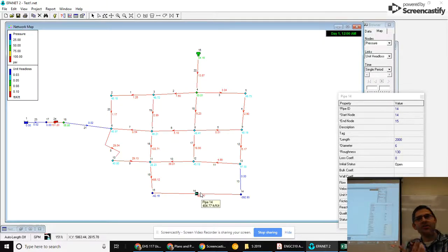So now if it's closed, I lose. But I can just lay it in parallel, it costs almost the same amount, and now I've got parallel pipes, a 6-inch and a 12-inch. Now if the 12-inch is out of service, I still need to be able to meet my pressure requirements. So maybe that's not a solution in and of itself. Maybe I need to put parallel 12-inch pipe here and here. Maybe I need to draw a new one from here to here or from here to here.